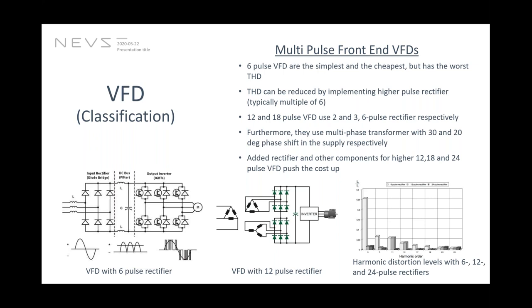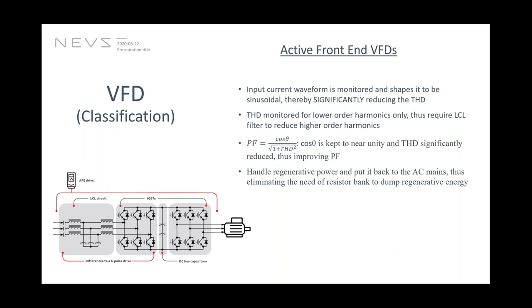But as you know, increasing the number of rectifiers will add on to the cost, and then there are costs for the other components like the multi-phase transformer that needs to be implemented. So in that case, I think it would be cost equivalent or even cost effective to use active front-end VFD. So basically, the difference between the multiple pulse and the active front-end is that instead of using a rectifier, you use IGBT switches even to rectify.